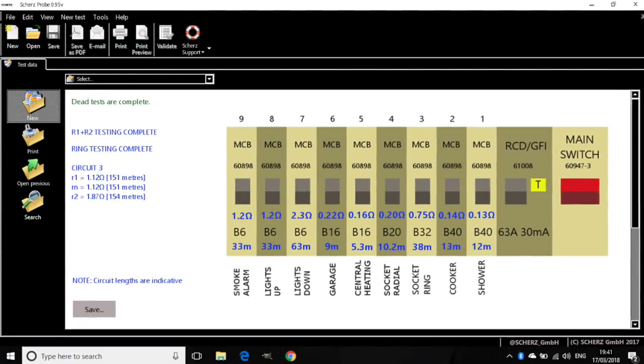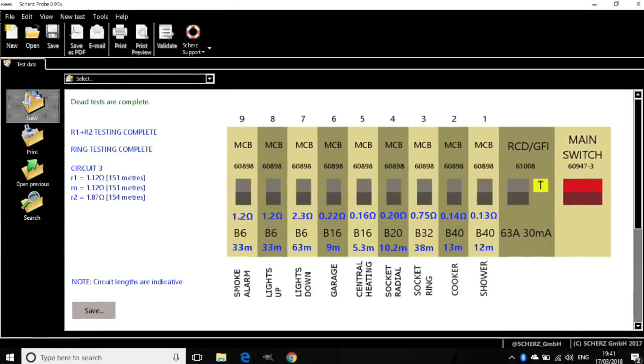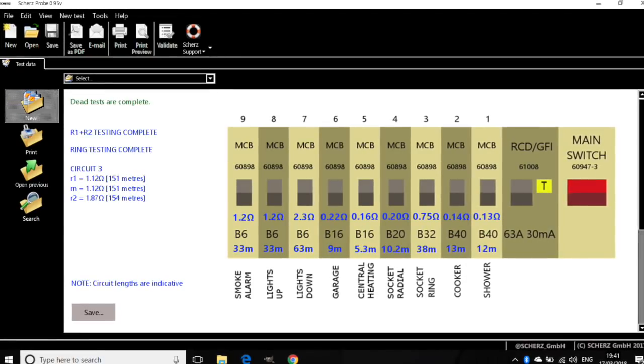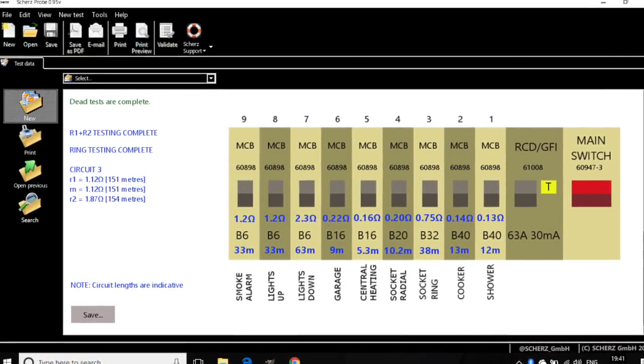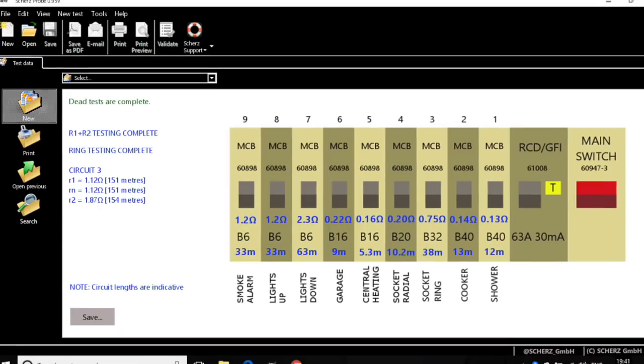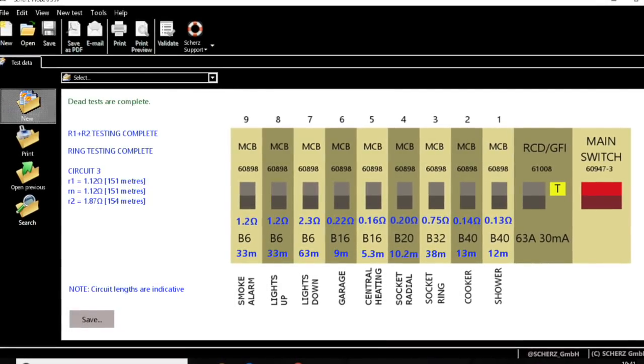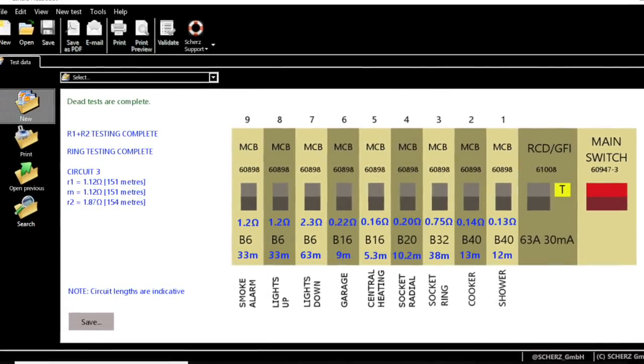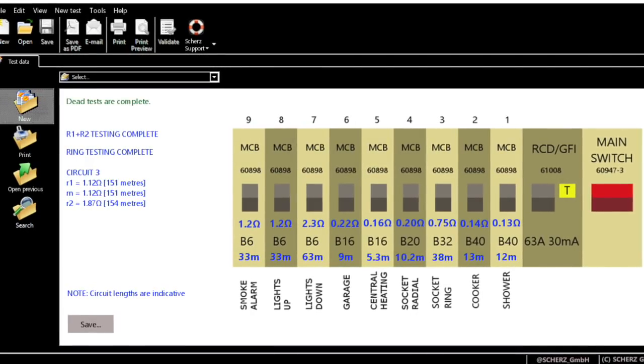The app divides the result by the known resistance per metre for the stated cross-sectional area of the wire to calculate the circuit length. It's able to test each circuit at the same time and without any physical disconnection of the wiring in the consumer unit by using frequency separation of its own internally generated low voltage AC carrier wave.